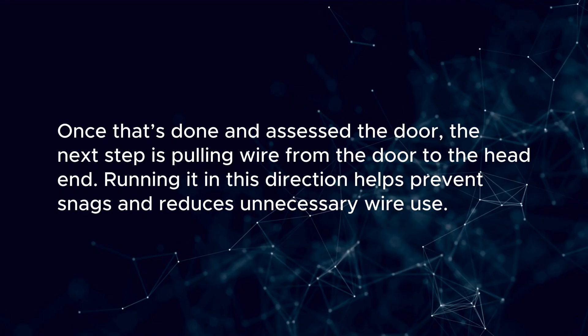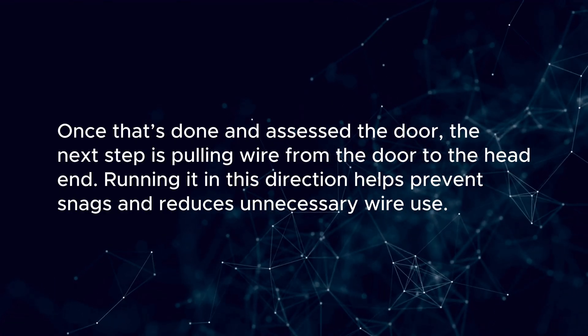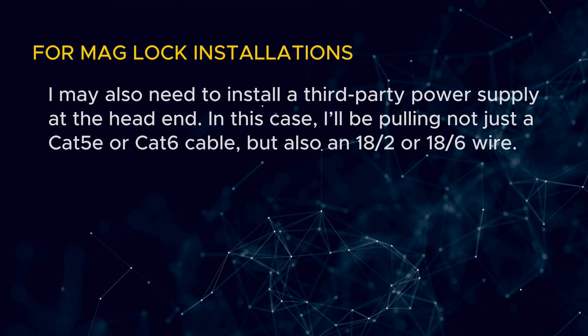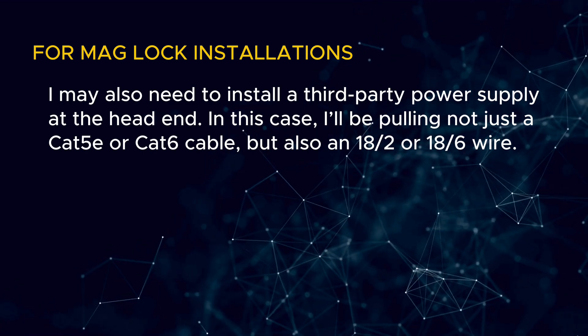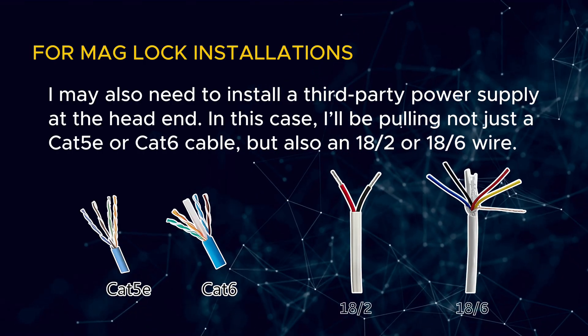Once that's done and I've assessed the door, the next step is pulling wire from the door to the head end. Running it in this direction helps prevent snags and reduces unnecessary wire use. For maglock installations, I may also need to install a third-party power supply at the head end. In this case, I'll be pulling not just a Cat5e or Cat6 cable, but also an 18/2 or 18/6 wire.